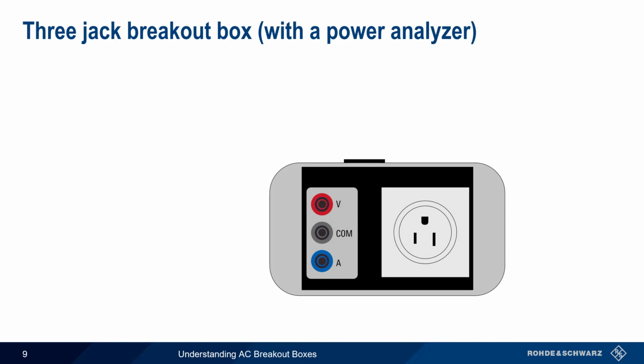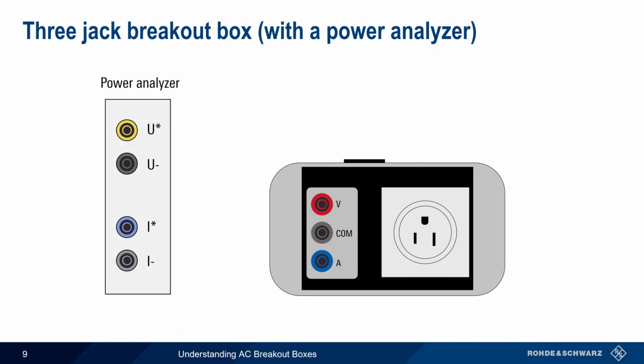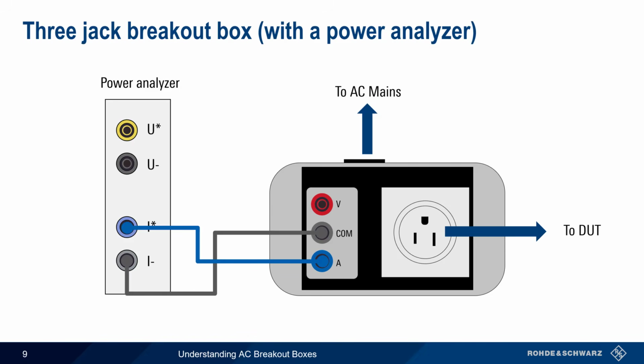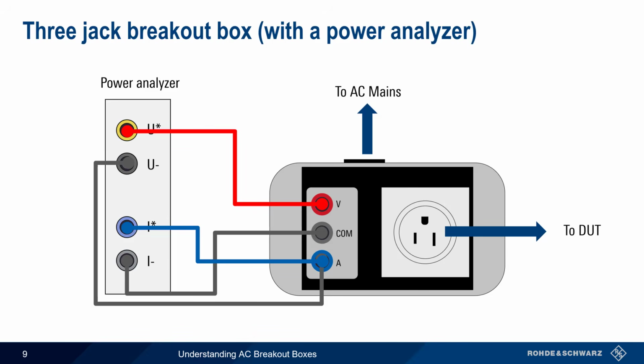The last example we'll look at is connecting a 3-jack AC breakout box to a power analyzer. The AC mains and DUT connections are made as in our previous examples. Current connections to the power analyzer are made between the current and common jacks on the breakout box. But the voltage measurement connection is made between the voltage jack and the current jack. Note that in this case there is no need for a jumper between the current measurement points.